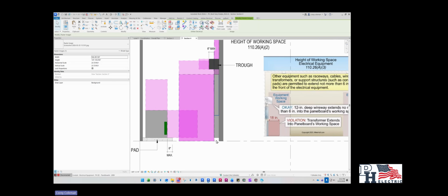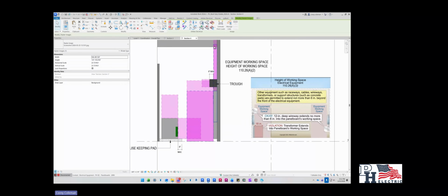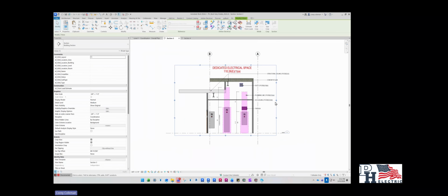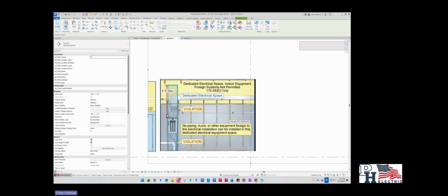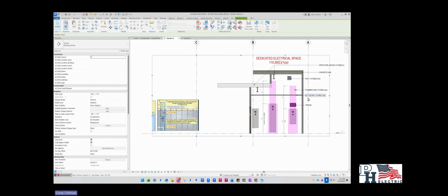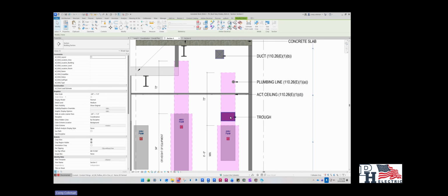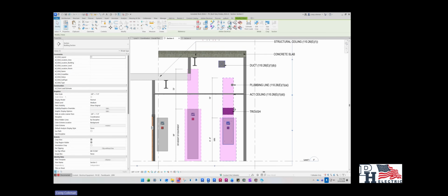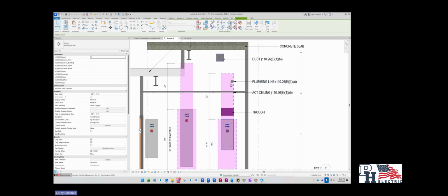And then lastly, we're going to talk about the dedicated electrical space. This is the space that lives from the panel underneath it all the way up to 6 feet above the panel itself, and that's the dedicated electrical space. What this is saying is that if something lives within that space, it has to be electrical in nature or an electrical installation. For instance, if this trough is here, this is okay as long as it doesn't stick out that 6 inches into the working space. But this plumbing line that lives within that 6 feet above the panel, this is a code violation. So this plumbing pipe would have to move.